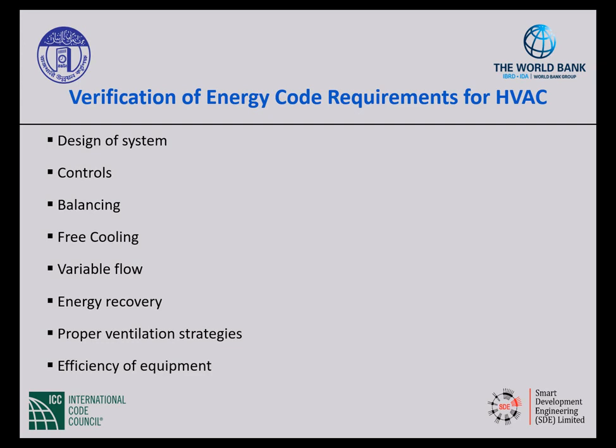When it comes to controls, that's the most important issue, right? It's also the hardest one. Not a lot of people understand mechanical controls, and so they don't know how to look for that sequence of operation or to look for those controls that shut things down when they're not needed. So I see a lot of times, yes, they've put in a time clock, or yes, they've put in their thermostat, but has anybody opened it to see that those settings, they have that 5% deadband, so they're not doing simultaneous heating and cooling. They have those settings set to where they're not running on, they have the 3 different day types per week, and they have their backup power to keep it going.